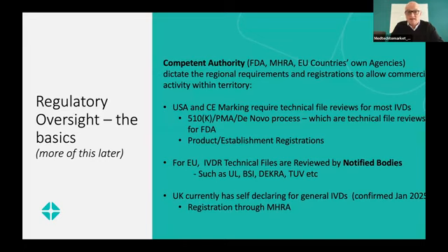So in the USA and with the CE marking, that means you require a technical file for most in vitro diagnostics. In Europe, it's roughly about 80% of all diagnostic tests that need to be technical file reviewed, and in the US, there's varying degrees. You'll hear these expressions: 510K, pre-market approval, or de novo. That just depends on what your technology is and how new and novel it is. You also need to register your product as well as the establishment within these regions.